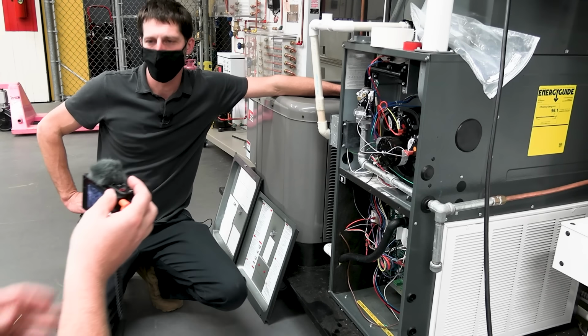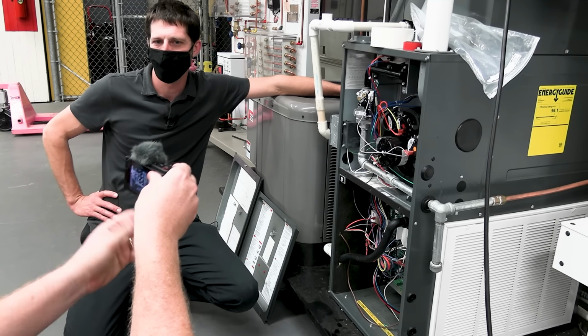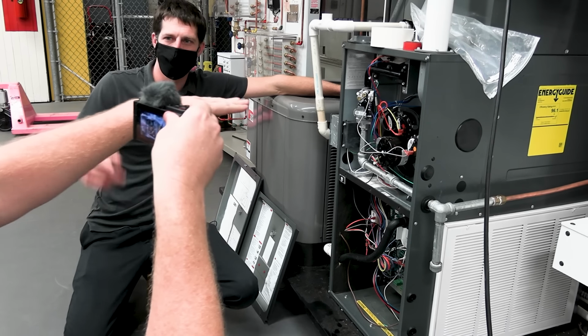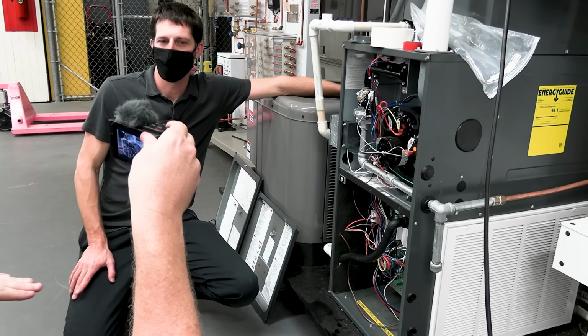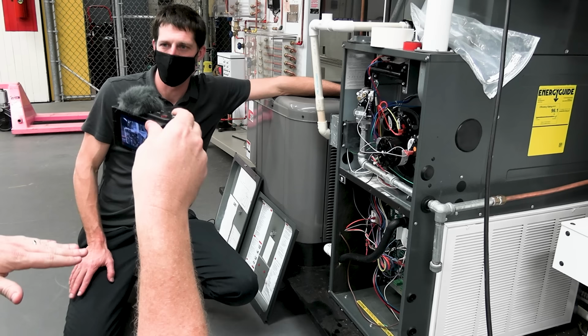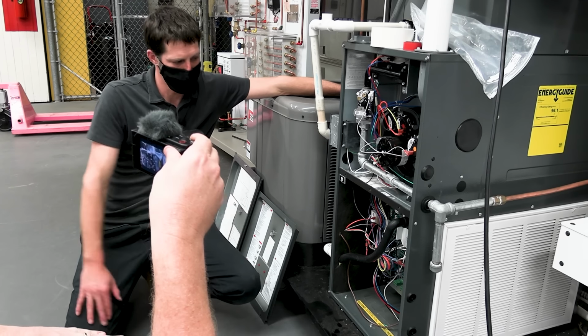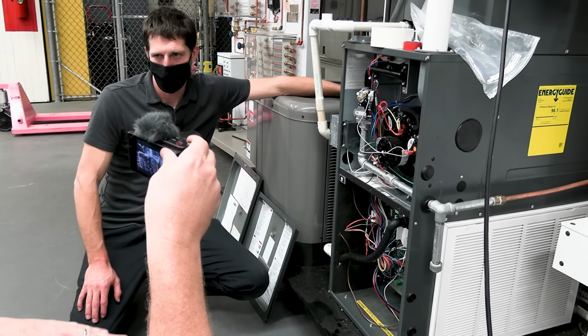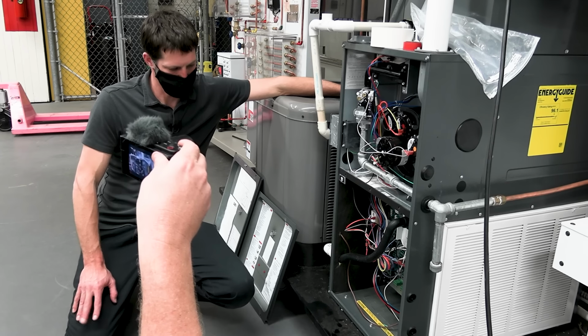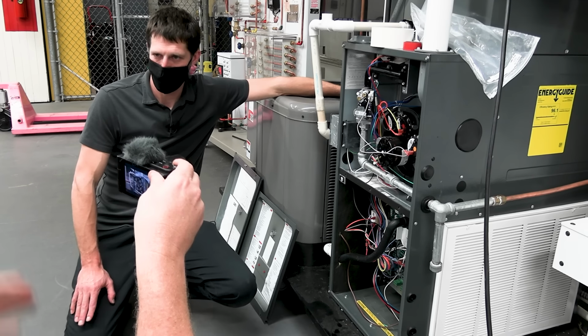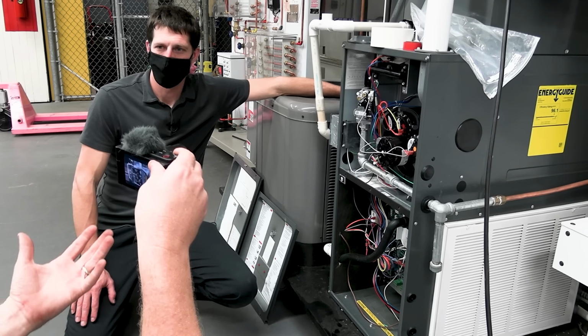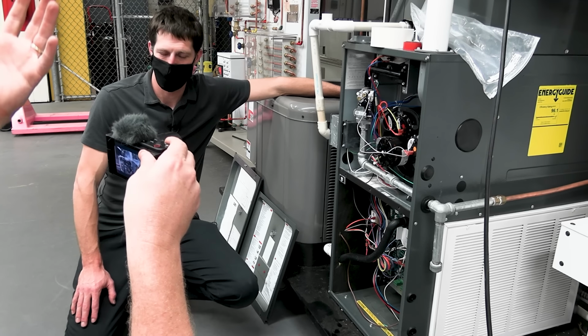Yeah, I would assume that you would have your primary heat exchanger, and then you'd have your secondary heat exchanger, but that isn't why, because where's the cooler air? Right. The cooler air is at the bottom, and which one is the cooler coil? The secondary heat exchanger, right? Your secondary heat exchanger, you're extracting that last little bit of heat out.